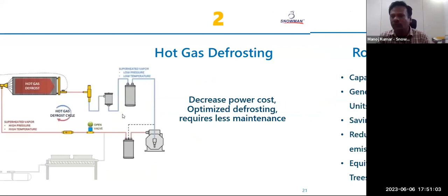How we do hot gas defrost: in simple terms, the discharge gas is applied to the evaporator during the defrost cycle, and it removes the ice. There is a small video animation here. The concept is that the discharge pressure from the compressor is applied to the evaporator during the defrost cycle, removes the ice, and comes back. So we are able to remove the ice with only 2 defrosts in a 30 minute duration.